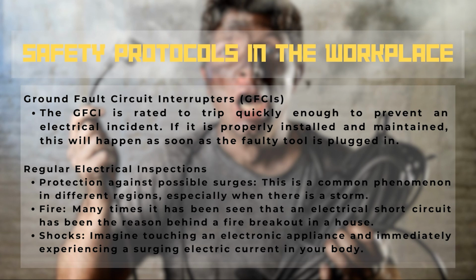Safety protocols in the workplace. The GFCI is rated to trip quickly enough to prevent an electrical incident. If it is properly installed and maintained, this will happen as soon as the faulty tool is plugged in. If the grounding conductor is not intact or of high impedance, the GFCI may not trip until a person provides a path. In this case, the person will receive a shock, but the GFCI should trip so quickly that the shock will not be harmful.